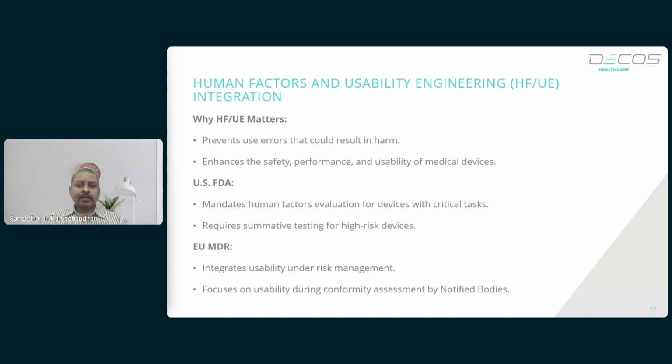On the other hand, EU MDR stresses usability as part of the General Safety and Performance Requirements (GSPR) under Annex 1. Usability is evaluated as a part of the device's risk management, and manufacturers must document how usability contributes to the overall safety and performance of the device, which is outlined in the standard IEC 62366.